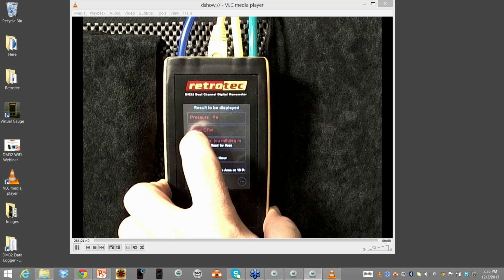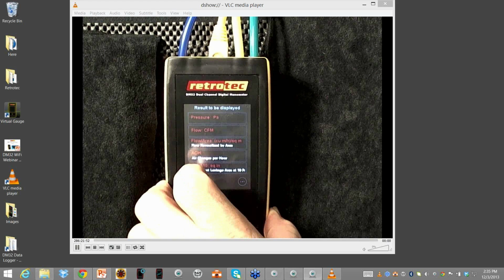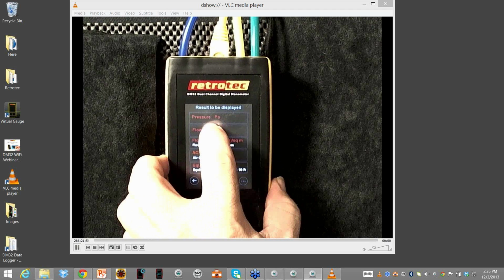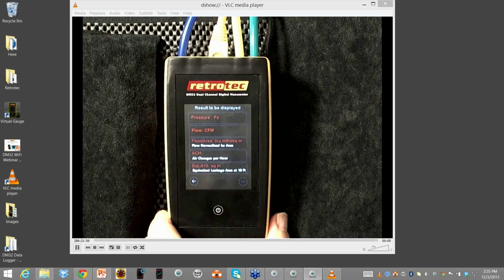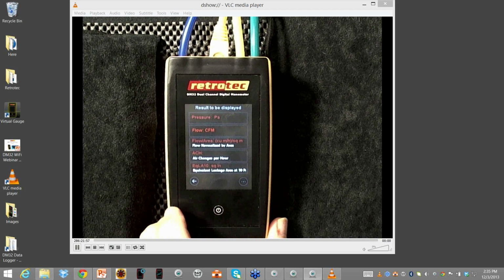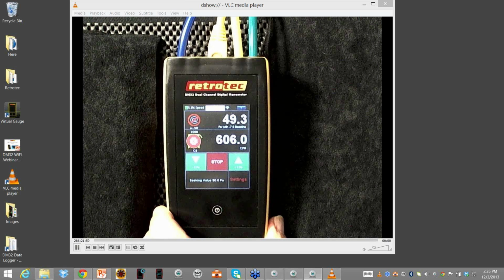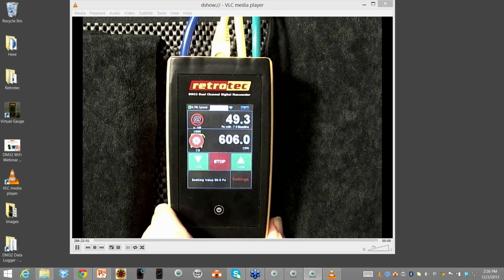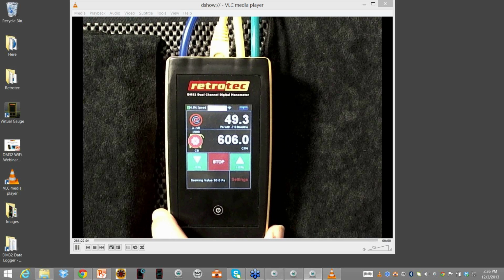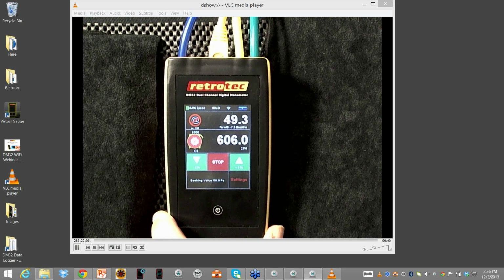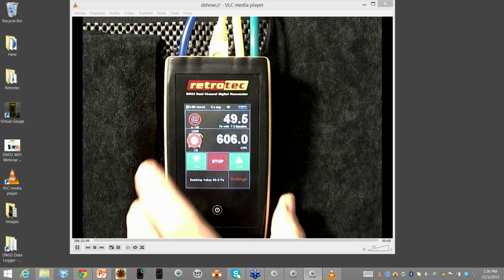So if I wanted to know what the CFM was at the exact same time, I press CFM and go back. It's hard to see, but now I can determine that I had 606 CFM if I wanted to calculate both or see what my results were. Press channel A again, and it goes back.